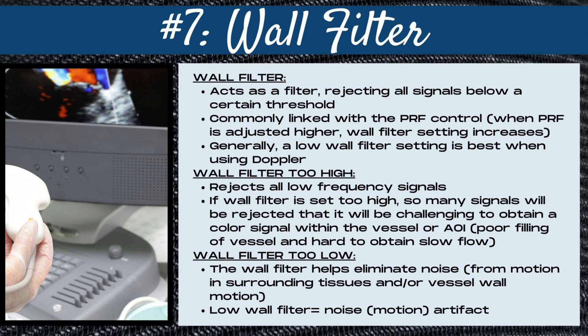The next setting in our color Doppler optimization checklist is the wall filter, which acts as a filter — it rejects all signals below a certain threshold, and this is commonly linked with the PRF control. When the PRF is adjusted higher, the wall filter setting also increases. Generally, a low wall filter setting is best when using Doppler. When the wall filter is too high, it rejects all low frequency signals, making it challenging to obtain a color signal within the vessel and doubly hard to obtain slow flow. When the wall filter is set too low, you'll have more noise or motion artifact, as the wall filter helps eliminate noise from motion in surrounding tissues and from the motion of the vessel walls.